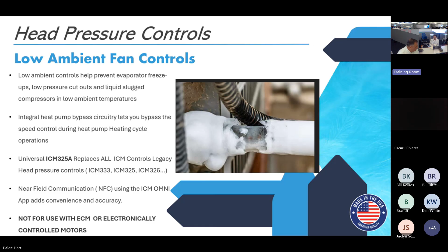Now, one thing that's important for the sales guys as well is that these are not meant for electronically commutated motors. For this group that's not as important, but for the salespeople it is very important. Electronically commutated motors already can vary their speed electronically, and these do not work with that type of control. These are for standard, what they call permanent split capacitor motors, or motors that have a capacitor. AC motor with a capacitor. So the old-fashioned type motors, just regular old motors, not ECM. We have other head pressure controls, like the ICM 713, that does work with electronically commutated motors, but not these type. These are for your standard controls, air conditioning units, refrigeration units.